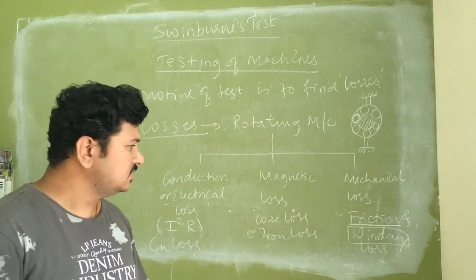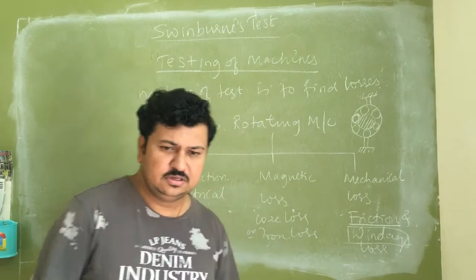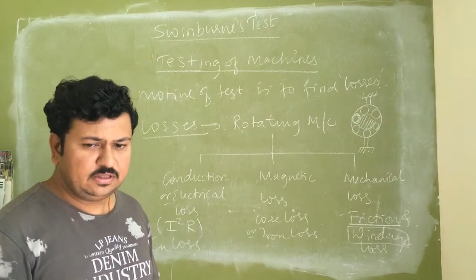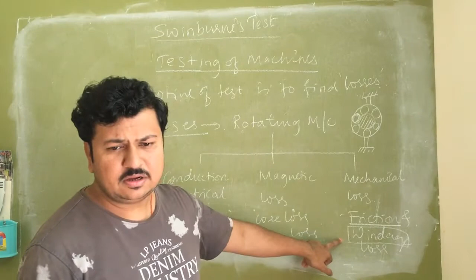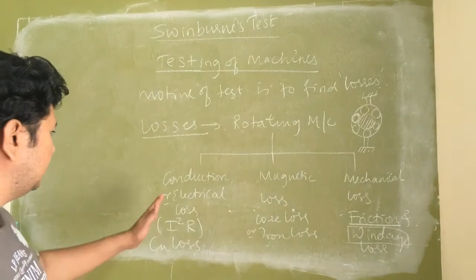Don't get misconceptualized that windage loss will exist in the winding. No, windage loss is a part of mechanical loss. Mechanical loss occurs due to mechanical operation. So when there is friction between the rotor and the air in the air gap, the energy lost due to that is called windage loss. So these are the three types of losses we get in a rotating machine.